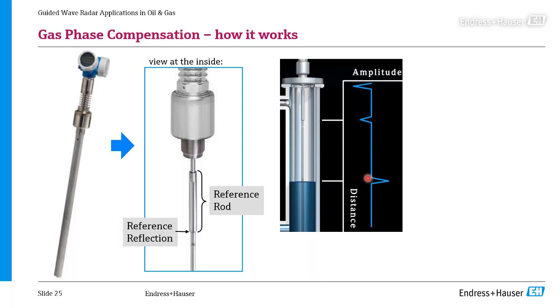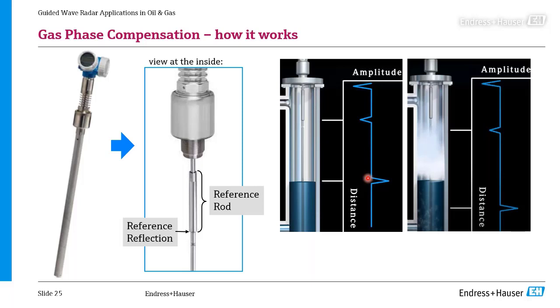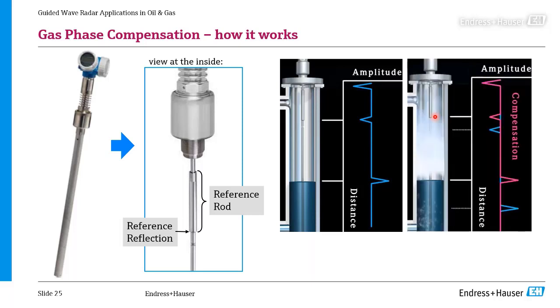Now what happens when there's a lot of steam in this bypass? Here you see the steam, and if you look at the signals, this signal has moved downward - it's not where it should be, since it should actually be around here. But the good thing is we know exactly where it has to be, because we know by the millimeter where the end of the reference rod is. You'll also notice the level measurement is no longer correct - it shows a much lower level than actually present in the bypass. But thanks to the reference rod signal, and our knowledge in the device and algorithms of where it should be, we can calculate back and compensate for that.